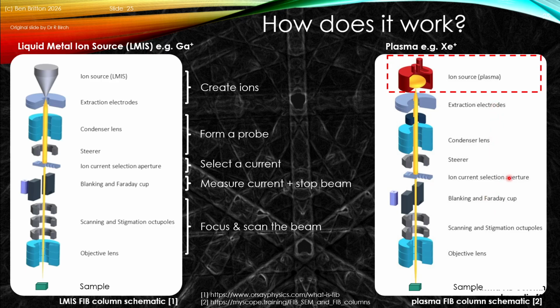I'd say one particular difference might be that you would change the ion current selection aperture, and that can be because the plasma could be more aggressive and could damage the apertures faster. So you might want a more radiation hard aperture strip for a xenon FIB. The rest of this is incredibly similar in that structure.